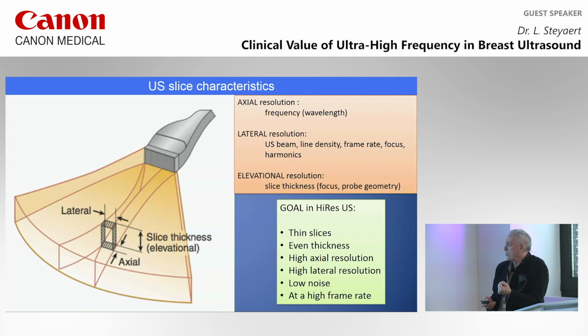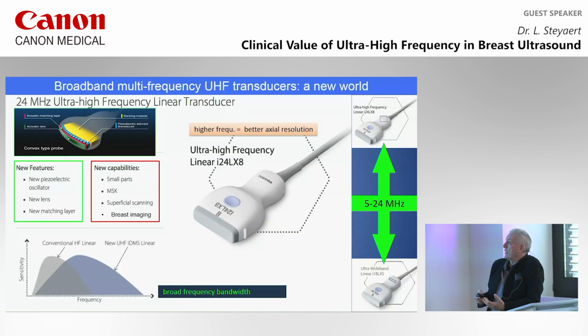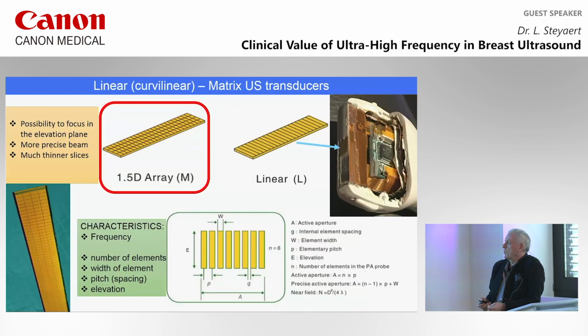So what we want in high resolution ultrasound is thin slices with an even thickness from top to bottom, with a high axial and lateral resolution, with a low noise image and at a high frame rate. That's the ideal situation. And now with the new transducers, we have broadband multi-frequency, ultra-high frequency transducers, and this really opens a new world, not only in breast imaging. We have frequencies going up to 24, and now on the booth you will see up to 33 megahertz. We have a large bandwidth transducer, so that with two probes we can cover frequencies from 5 to 24 megahertz. And that's very interesting for a lot of applications and also, of course, for breast imaging.